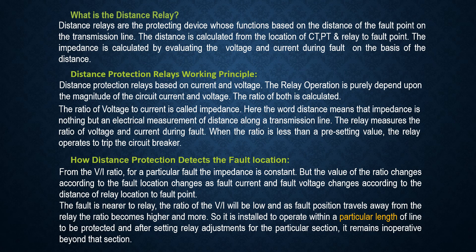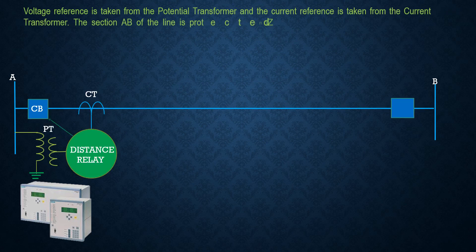The relay is installed to operate within a particular length of line to be protected. After setting relay adjustments for a particular section, it remains inoperative beyond that section. Voltage reference is taken from the potential transformer and current is taken from the current transformer. The section AB of the line is the protected zone, and the impedance is collected from conductor line data.